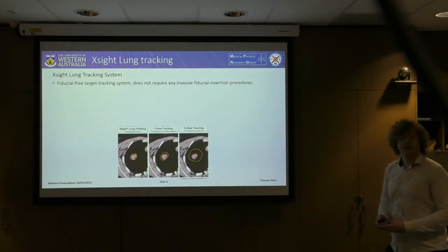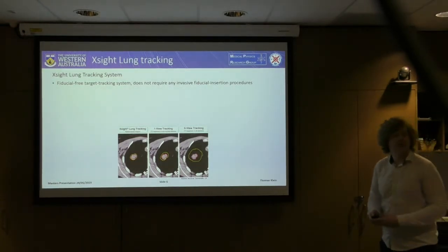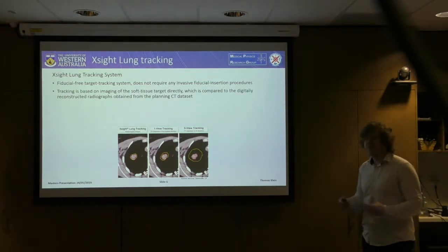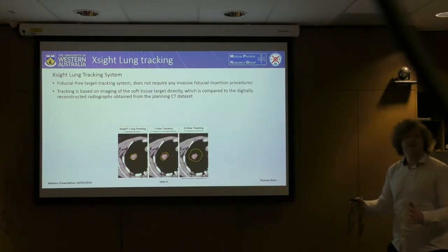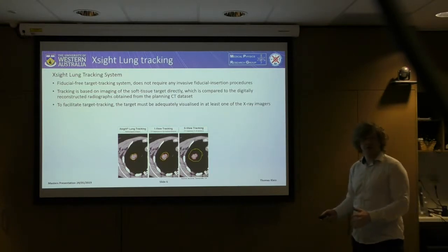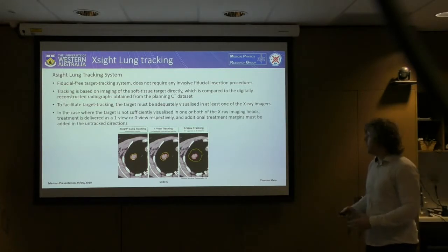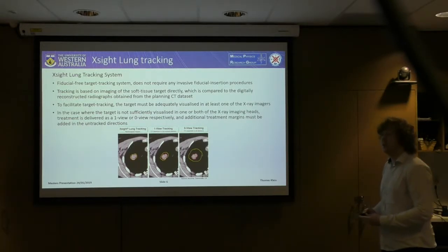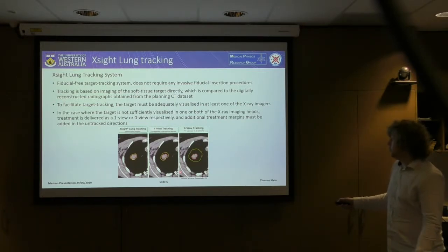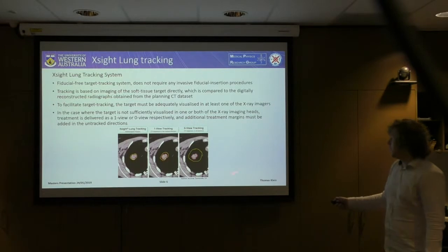In contrast, the Xsight Lung tracking system is a fiducial-free system requiring no invasive insertion procedures. Tracking is based on imaging the soft tissue target directly, compared against the planning CT dataset to determine the tumour's positional information using intensity-matching algorithms. The target must be adequately visualised by at least one x-ray image. If only one view is available, additional margins must be added in the untracked direction; with zero views, margins are added in all directions.